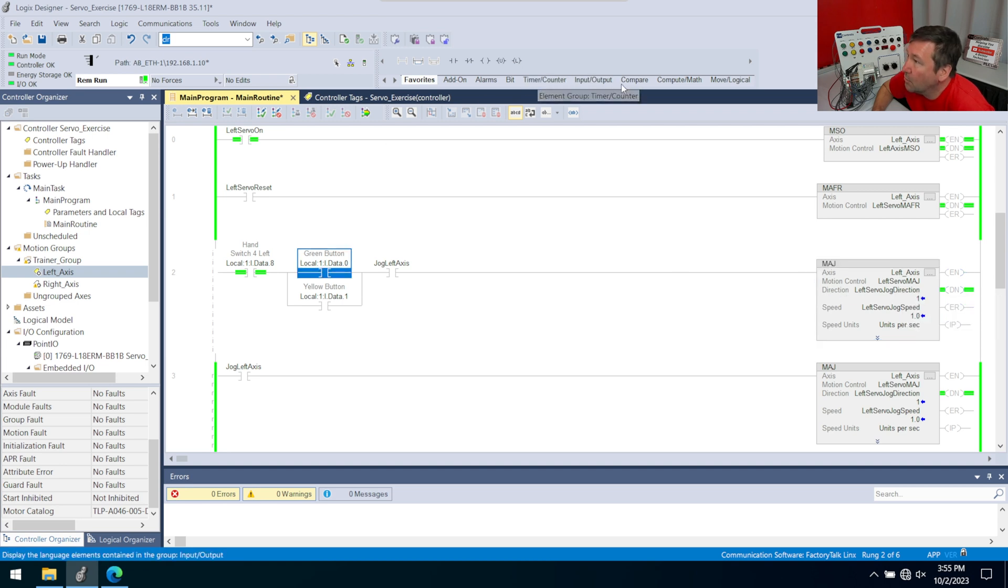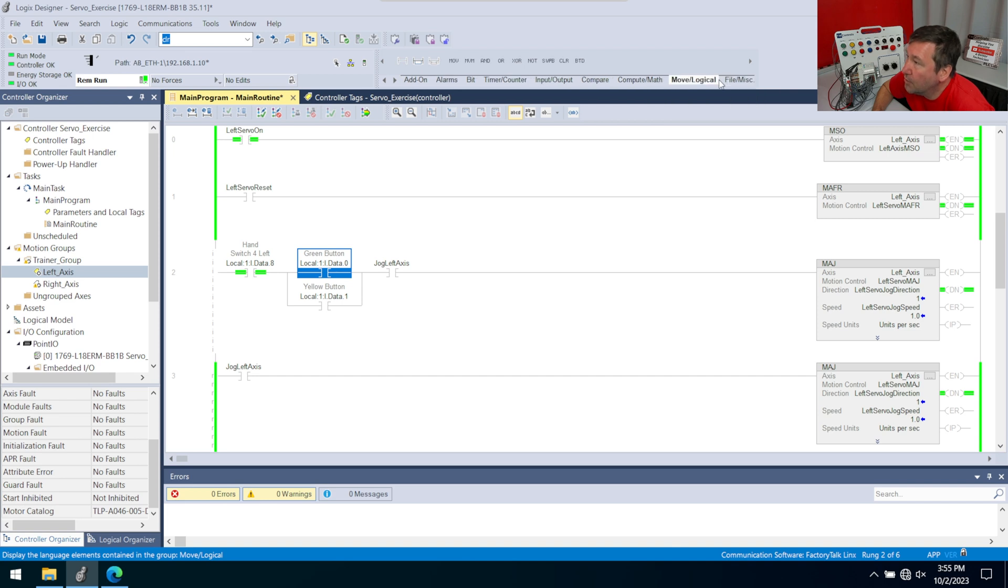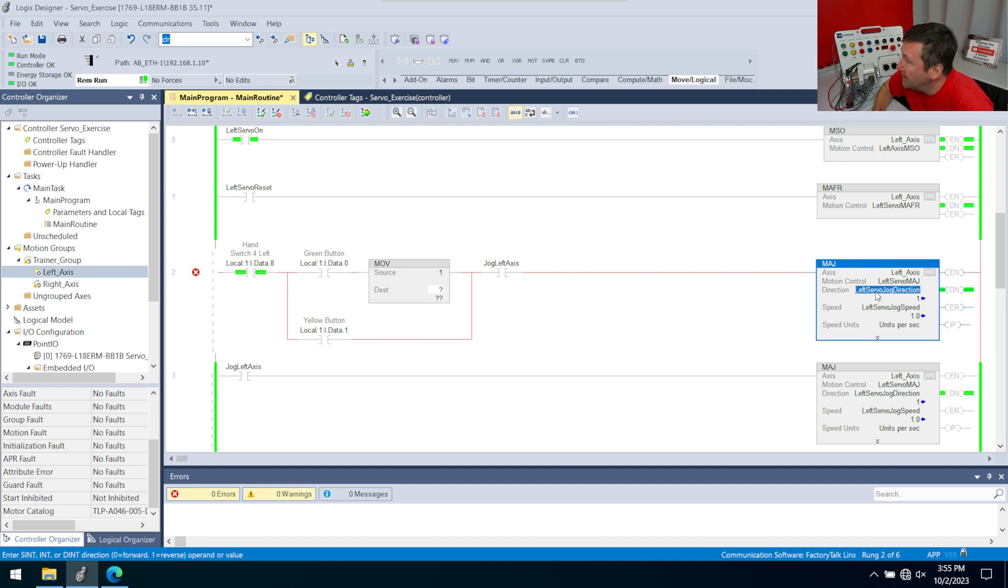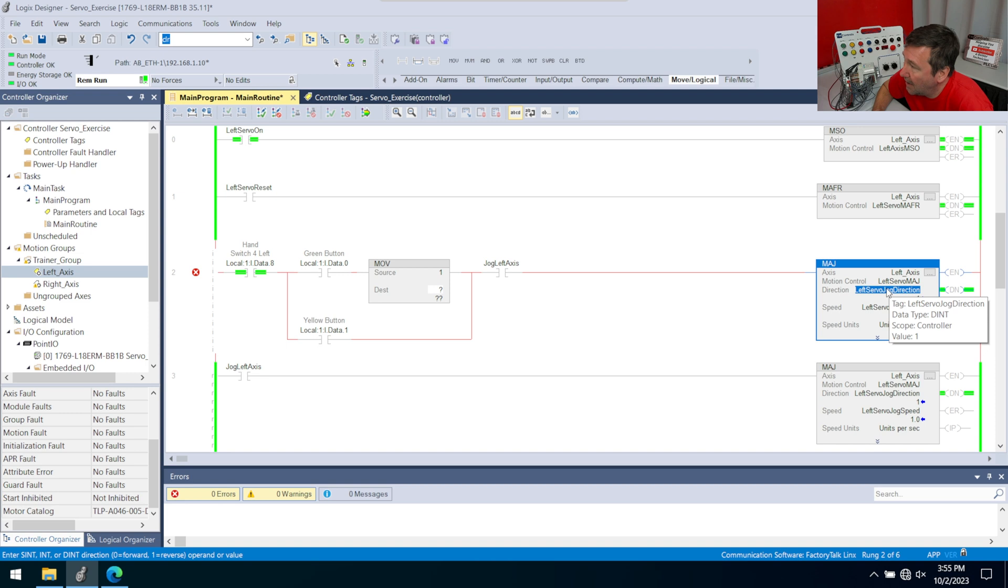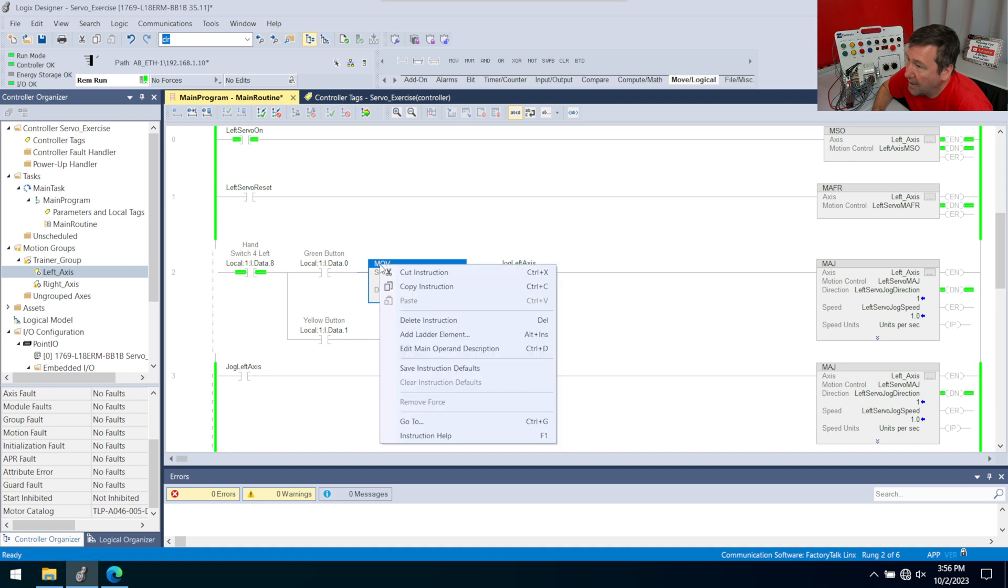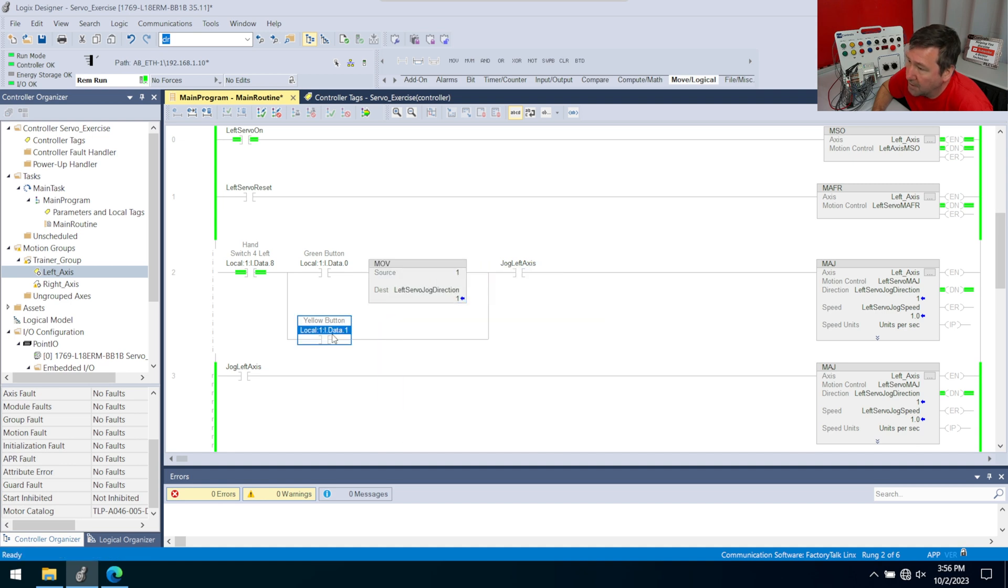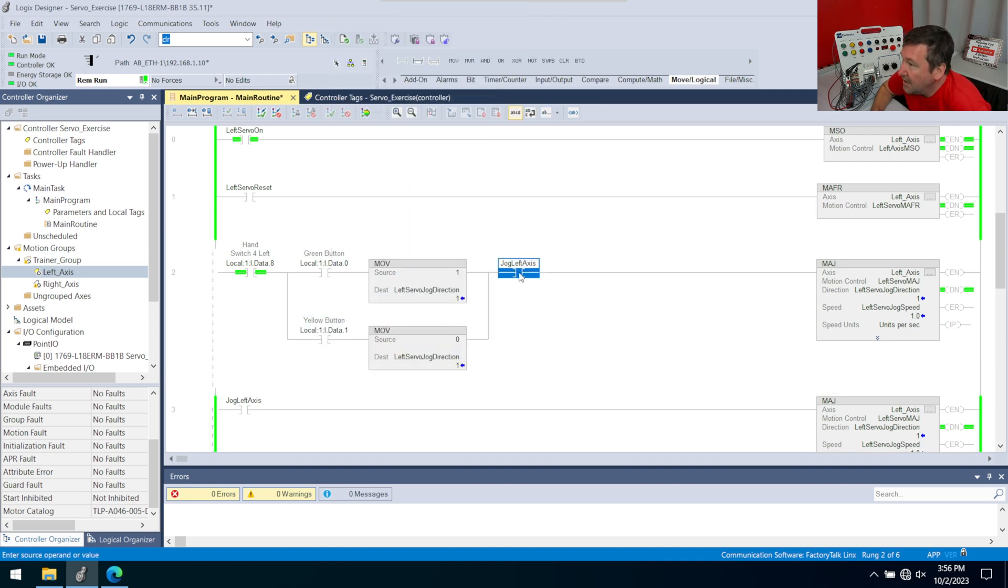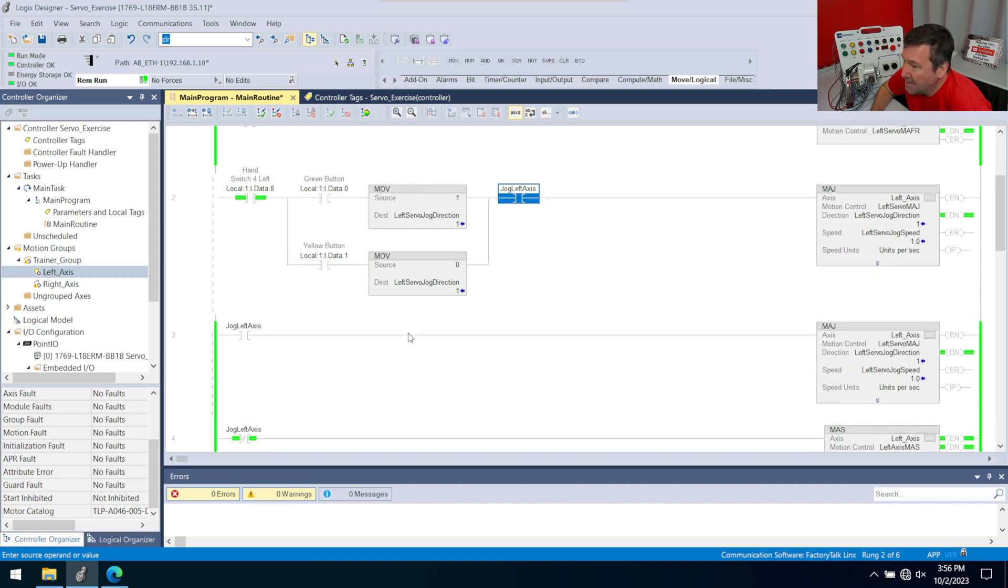So along with this, we are going to bring down a move instruction, which is on the move logical tab. We are going to move a value of one into this left servo jog direction. Instead of typing all that, I can simply click the tag, drag it over, and drop it right on this green box. Then we're going to right click that move and copy it, because we want a copy of it in this lower branch also. This will be a value of zero. So this replaces this left axis jog bit that we had earlier.